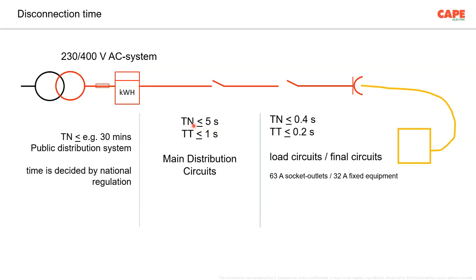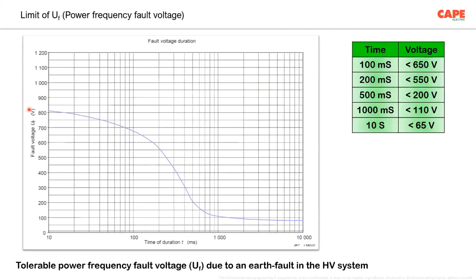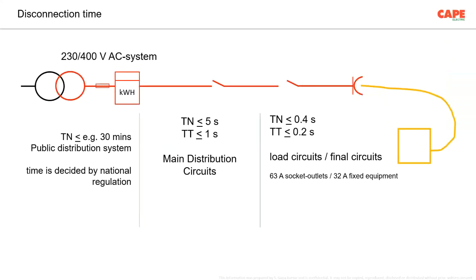Here, protective equipotential bonding means the metallic parts in your building are interconnected in such a way that there is no fault voltage, or the fault voltage is limited to a level lesser than this particular limit. And if you are not making protective equipotential bonding, then of course this 5 second and 1 second is not applicable. You have to go for the time which is of course specified in IS 3043.